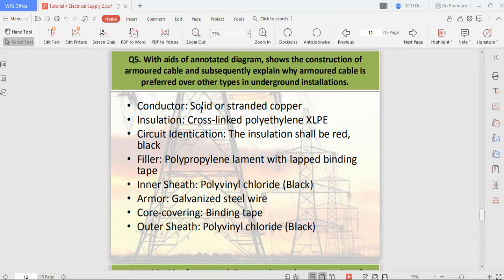What's the conductor? It's a solid or stranded copper. You have the insulation, which is polyethylene, and circuit identification should be insulated with red or black, and then you have a filler. Then you have your inner sheath, you have your armor to protect from any physical damage, and you have your core covering, and then your outer sheath.